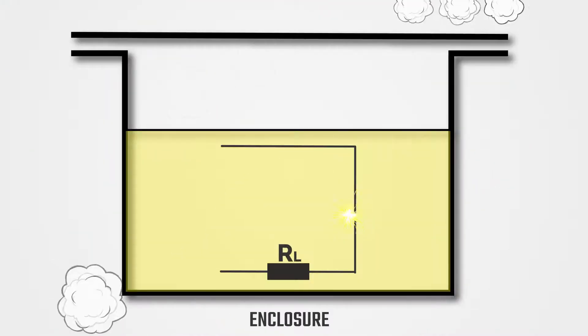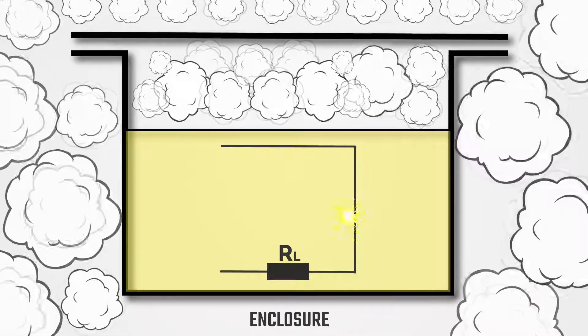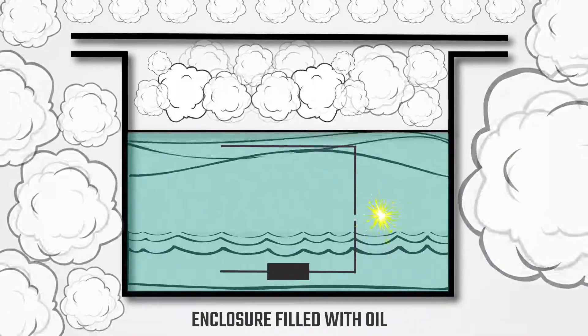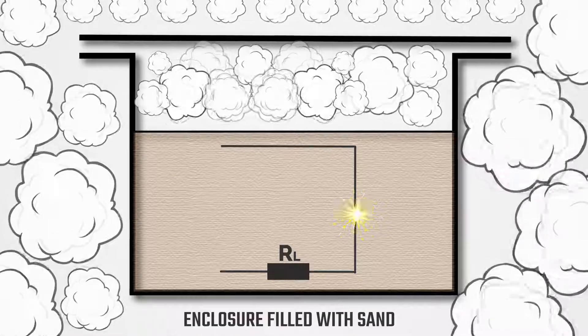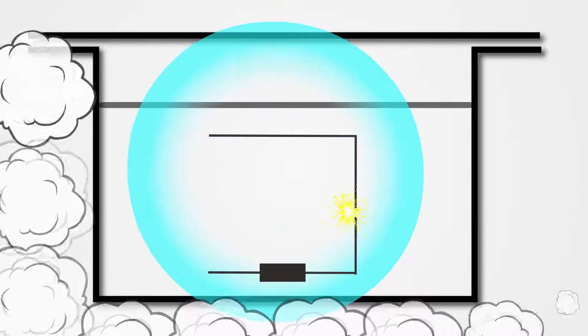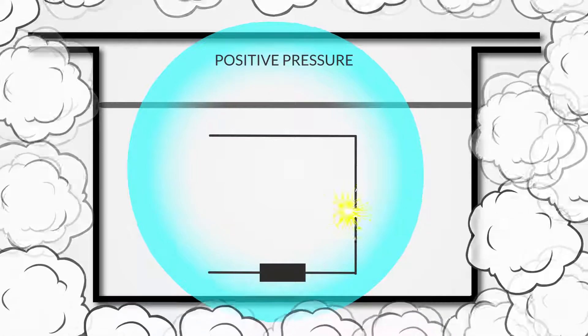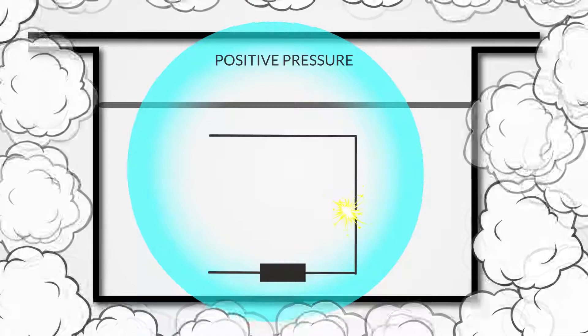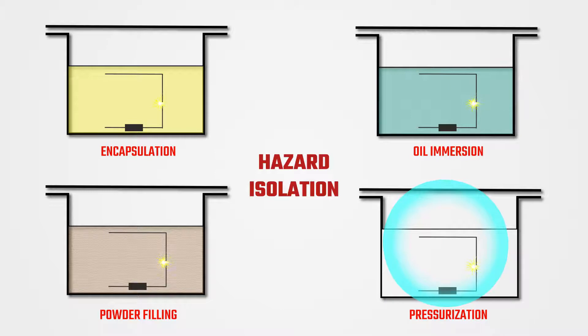The second approach involves isolating the source of ignition from the explosive atmosphere. The source of ignition — heated surfaces or sparks — is isolated from an explosive atmosphere by encapsulating the device in a resin or immersing it in oil. Or the device can be filled with sand, glass, or quartz particles that keep an ignitable mixture from forming inside. Or the enclosure can be purged and replaced by clean air or an inert protective gas, then pressurized so that the pressure inside is higher than the surrounding atmosphere, keeping an explosive atmosphere from entering. This approach is referred to as hazard isolation, and the protection techniques are encapsulation, oil immersion, powder filling, and purging and pressurization.